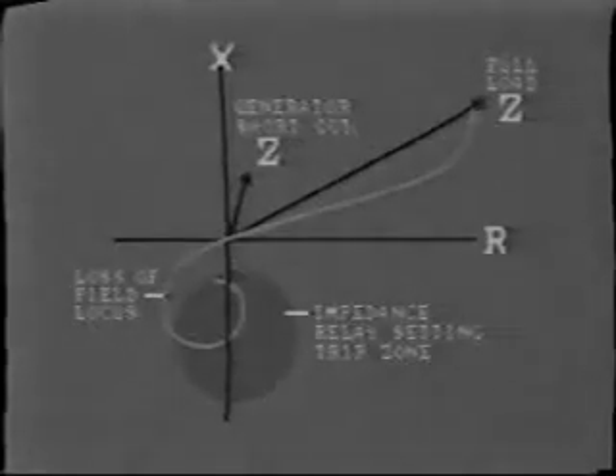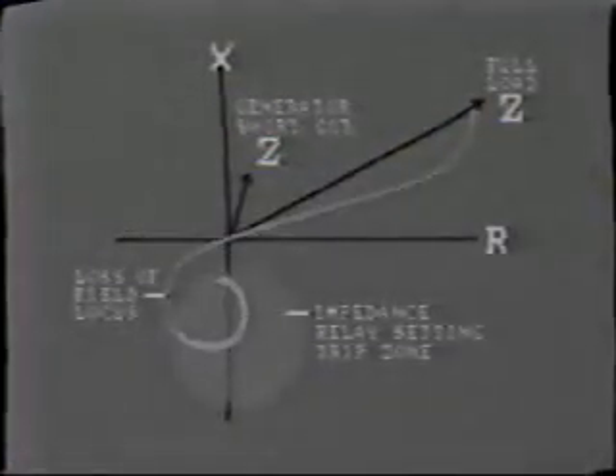Nowadays, loss of field is detected by measurement on the generator high voltage side. One method is to use a megavar meter set to operate when the imported, that is, negative megavars reach a high level, implying that the unit is operating as an induction generator. The preferred method is to install an impedance relay, which compares the state of voltage and current. During normal, full load operation, the impedance will be out here. A short circuit on the generator terminals will bring the impedance to this point. However, if a loss of field occurs, the measured impedance would move usually into the third quadrant due to the import of reactive power. Consequently, the loss of field impedance relay is set to operate in this zone.